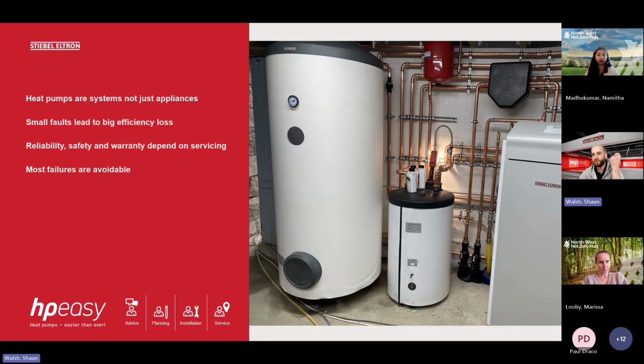Reliability, safety, and warranty. The reliability of the machine is dependent on a lot of factors. Like I say, controls, hydraulics, sensors, and things like this. And in terms of safety, we have the expansion vessel. If anyone is G3 qualified, this is a government regulation that you have to be qualified to install these expansion vessels. So it is a safety requirement which needs to be checked annually. And most failures are avoidable with heat pumps if proper service and maintenance is carried out. Okay.